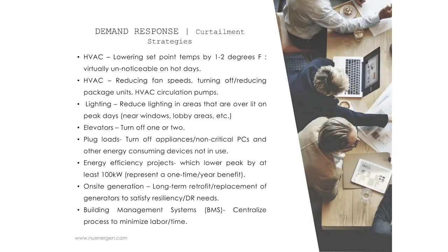So what are some common strategies for demand response? Even though most facilities are unique, there really are just a handful of strategies. First and foremost, you look at the base building HVAC systems, those sources of demand for electricity - chiller plants, fan systems on HVAC systems, the supply fans, the return fans. It's lighting - you don't pick up too much kilowatts from lighting, typically turning off some lights in maybe a lobby, but you can pick up some. Turning off maybe an elevator or two or a bank or two in your building. Plug loads, energy efficiency projects, on-site generation, and BMS systems.